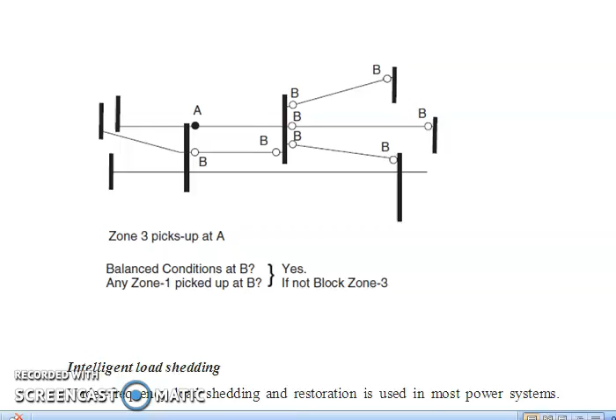Now if an overreaching zone of relay A picks up, then the PMUs at all the B locations can cooperate to determine if the apparent impedance seen by them represents a fault in the direct zone of any of those relays. If none of them sees such a fault, then clearly the pickup of an overreaching zone at A is due to something other than a fault and it should be blocked. Note that this action is to be taken only for balanced conditions at A and B locations. Since load encroachment or stability swings imply balanced operating conditions, the distances from which measurements are to be obtained are modest, so that the communication delay can be insignificant. So this is how supervision of backup zones takes place with the help of wide area measurement system.